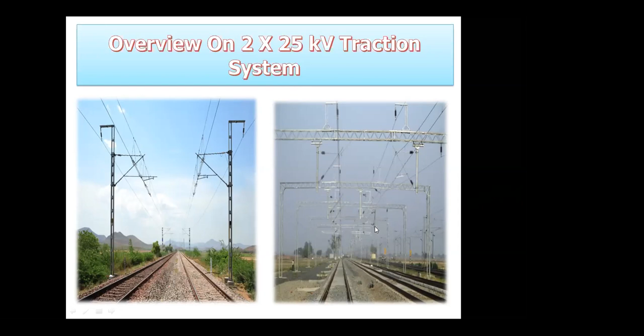The concept is simple: since the loco is drawing current from 25 kV, but the auto transformer is of 50 kV, the voltage drop in the system will be less. One TSS can feed a longer distance, or in other words, the same TSS can have more number of trains, and vice versa.